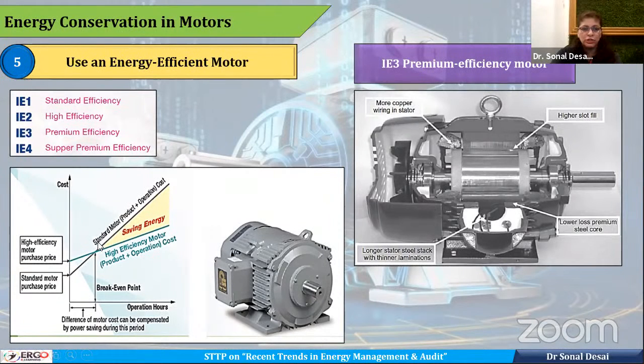And this particular triangle shows the saving achieved in its lifespan. And this particular diagram shows why premium efficiency motors are better. They have a higher slot fill, lower loss, premium steel core, longer stator steel stack, and more copper used in the winding. Because of this, these motors are better.